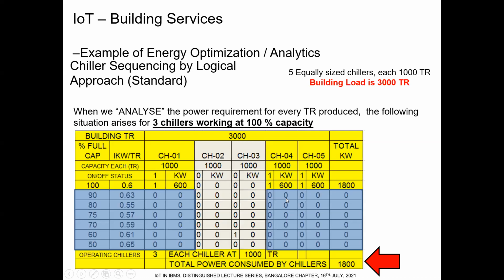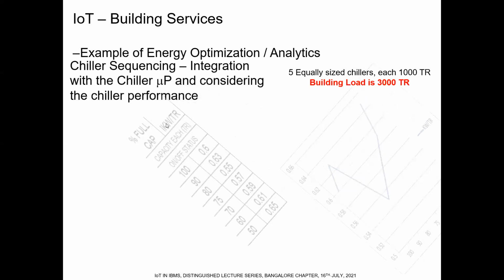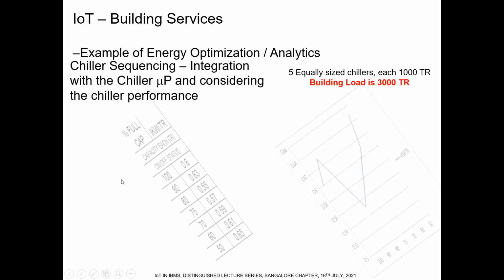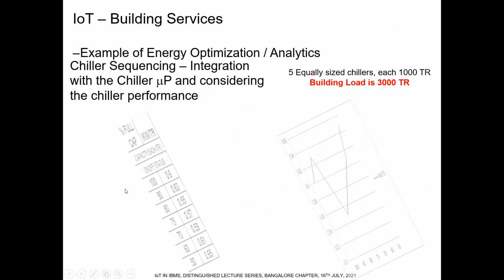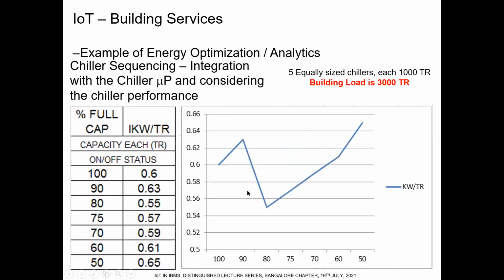With the general level of automation, 3 chillers producing 1,000 tons each, working at 100% capacity, would consume 1,800 kilowatts to produce 3,000 tons at the rate of 0.6 kilowatt per ton. This is the cataloged value of the chiller manufacturer. Instead of that, if the BMS vendor and the chiller vendor had interacted a little bit, they are now going further deep into the automation process. They are interacting on this table. The chiller manufacturer, for every particular model, has what is called a sweet spot.